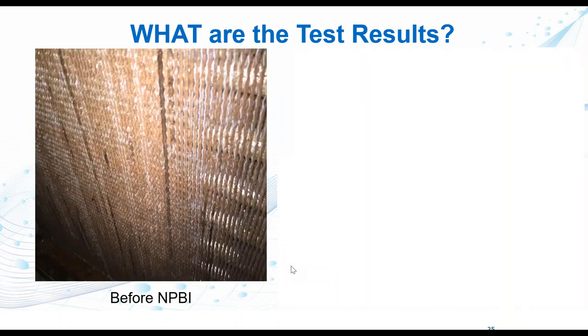Because I'm visual, I threw another one in. Here's a coil from a hospital in North Carolina. As you can see, this coil is covered in biofilm. And I'm going to digress for a minute. Sometimes when we clean a coil with steam or chemicals, we can make the surface of the coil look great. It looks nice and shiny. Unfortunately, what can happen is sometimes the dirt gets pushed further into the coil. And that's really true if we have coils that are 4, 5, 6 rows deep. It's not uncommon to see that happen.